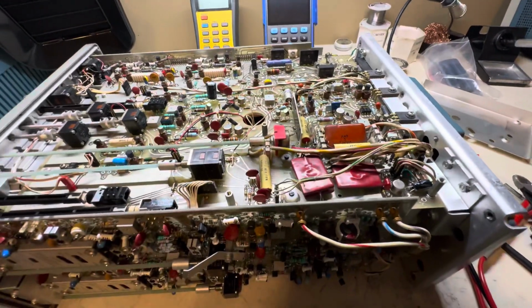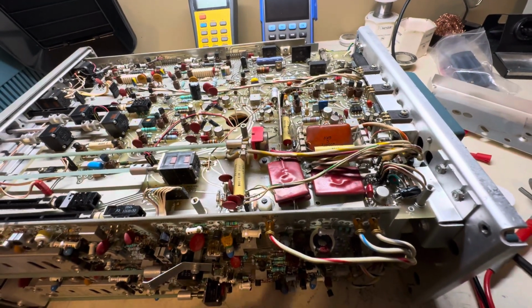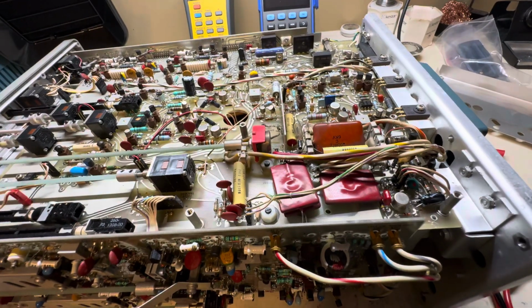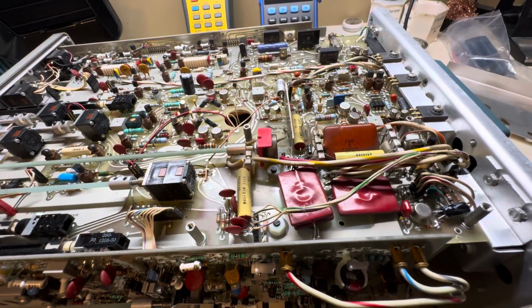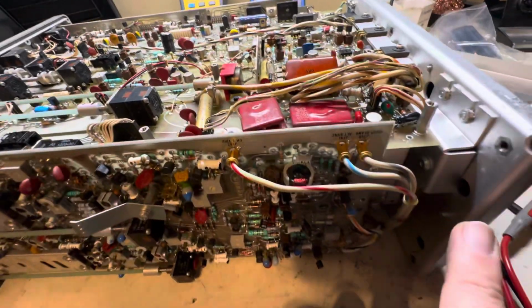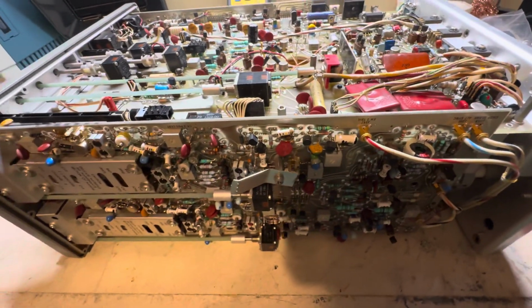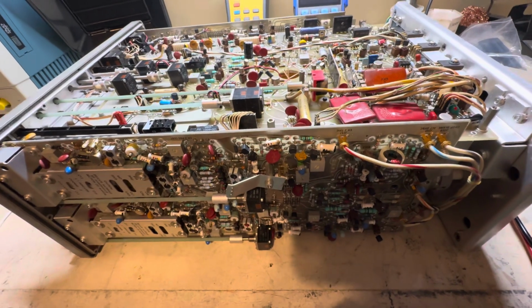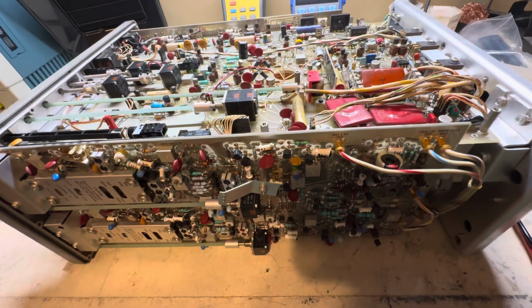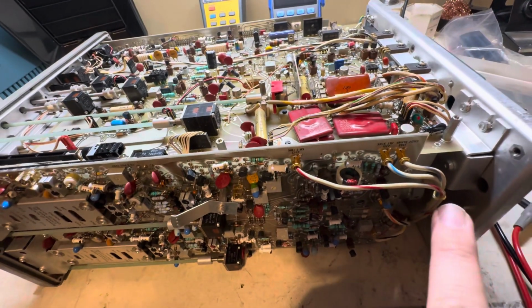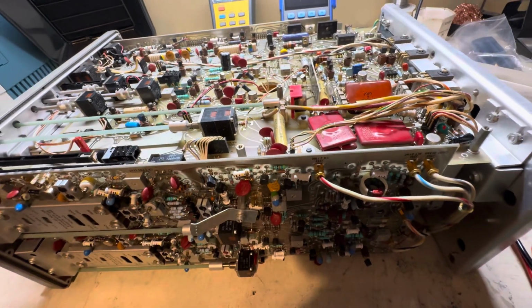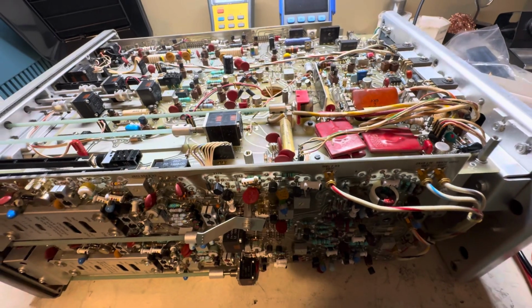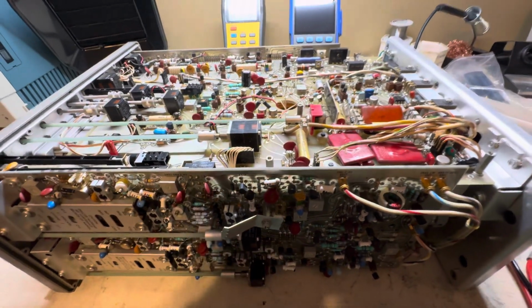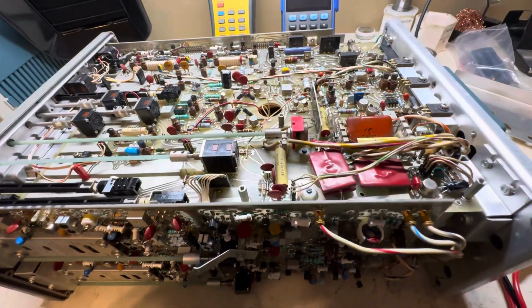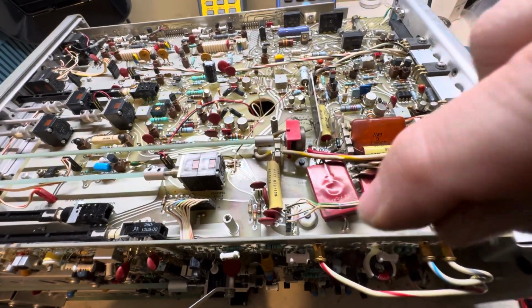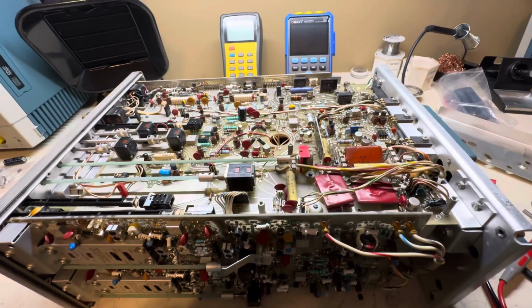Either way, I went ahead and did the next obvious thing since I know it's a common problem with these. I lifted that jumper, which lifts the ground strap, since I didn't feel like removing the whole vertical assembly. The proper way would be to remove the entire vertical assembly, then remove the shield covering the high voltage transformer and multiplier, and tape up that ground strap so it doesn't ground to anything. Right now if I turn the intensity up, it's going to ground right over here.